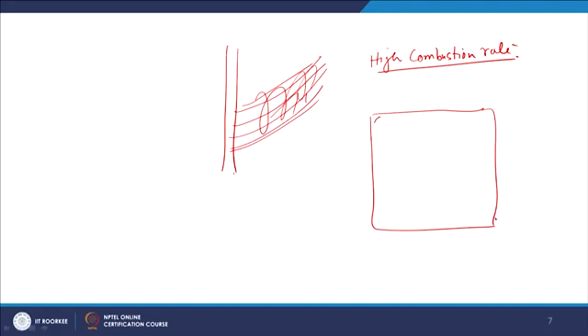In this burner, in a rectangle or a square, on the 4 corners, it is a combination of burners. 4 inlets are provided. In fact, there are 4 burners. At the center, suppose there is an imaginary circle, the outlet of each burner is tangential to this circle. So, a very good turbulence is generated here, which ensures the complete combustion of the entire combustible material in this space. So, tangential burners are very efficient burners.